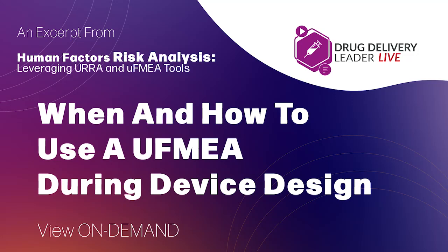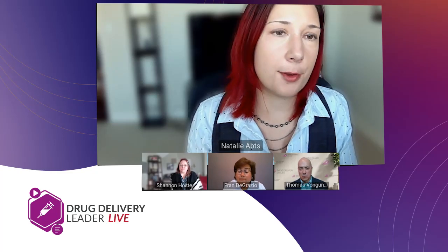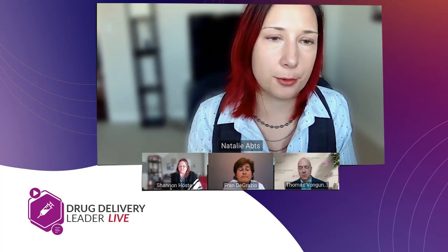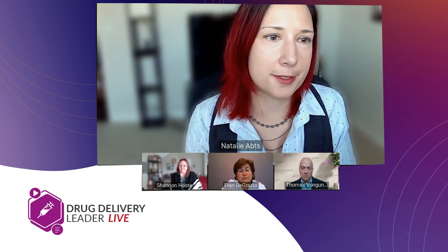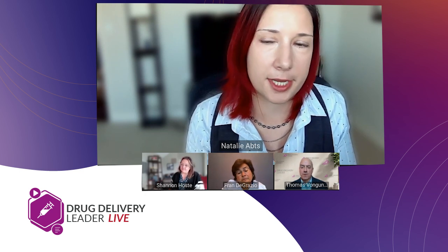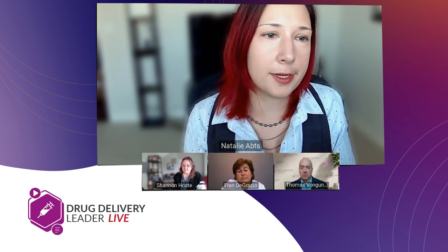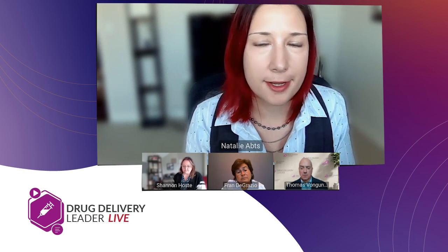What are we doing within our companies versus what we're actually giving to the FDA, right? And what they're asking for in the URRA, we're all compliant with 14971, right? And that talks about risk in a way that doesn't include everything that you see here in UFMEA, right? I think one of the major things is that the FDA has made very clear through all of their human factors guidances over the past 10 years or so that probability of occurrence is not something that they're really interested in when it comes to task criticality, right?